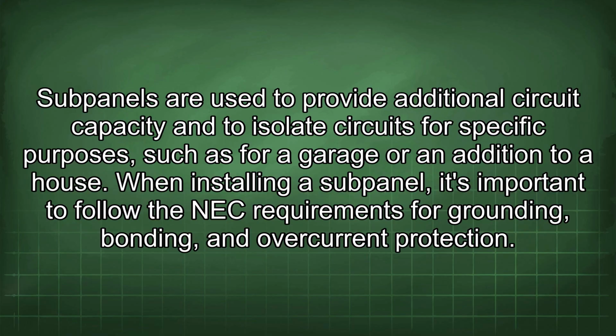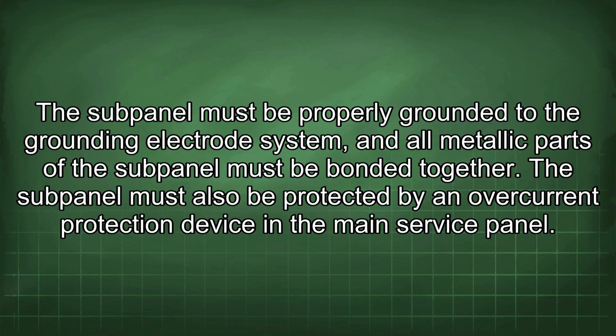When installing a subpanel, it's important to follow the NEC requirements for grounding, bonding, and overcurrent protection. The subpanel must be properly grounded to the grounding electrode system, and all metallic parts of the subpanel must be bonded together. The subpanel must also be protected by an overcurrent protection device in the main service panel.